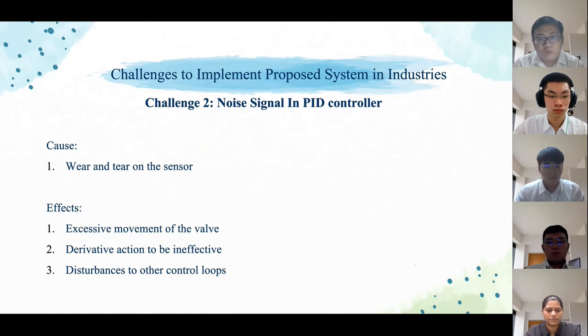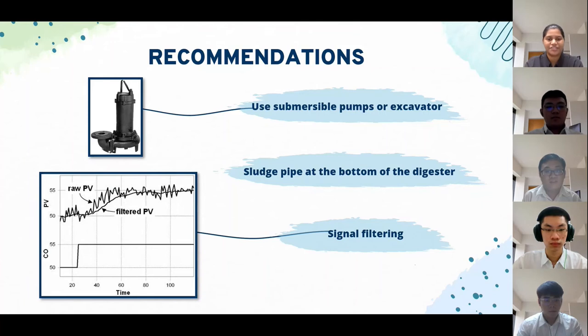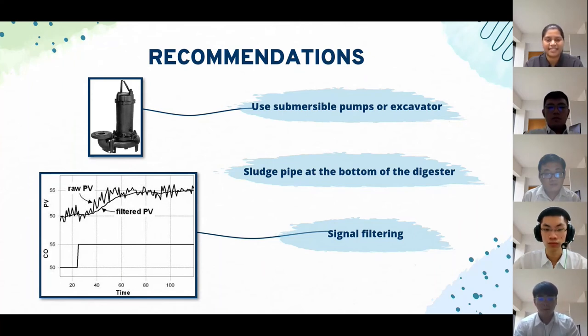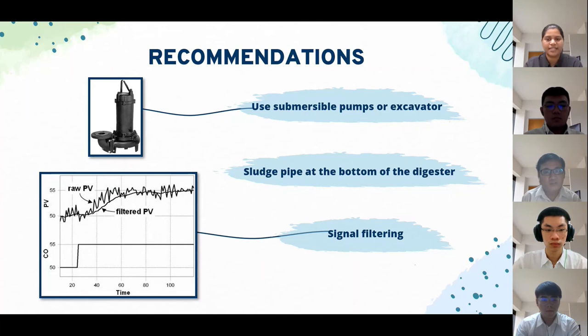Now let's move on to recommendations. The major challenges in treating POME using ponding systems are scum formation and solid sludge accumulation, as well as noise signals in the PID controller. There are three eco-friendly recommendations. The first is to remove scum and sludge using submersible pumps or excavators, then de-water and dry them to be used as fertilizer or for other land applications. The second is to install a sludge pipe at the bottom of the digester to remove accumulated solids. The third is the implementation of signal filtering. Typical industrial PID controllers include a filter on the derivative term expressed as a fraction of the derivative time, usually in the range of 0.1 to 0.2. Based on the graph shown in the slide, a filter is able to receive a noisy signal and yield a signal with reduced random variation, while retaining more of the true dynamic information of the original signal.